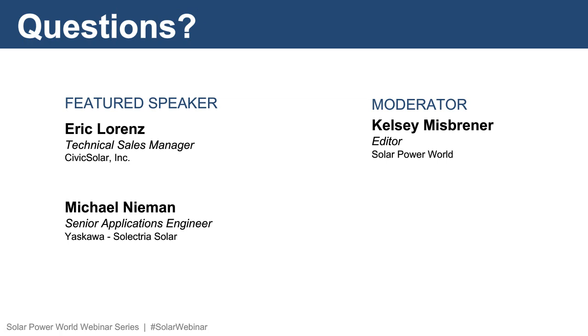All right, the next question. Can I jump in real quick from the equipment manufacturer standpoint? So what we're doing, speaking for Solectria, is our Transformerless three-phase string inverters. We don't solidly ground the DC side of the array. We incorporate overcurrent protection currently on both poles of the DC array, which is in compliance with the 2014 code. And we additionally break both legs of the array through the DC disconnect switch.